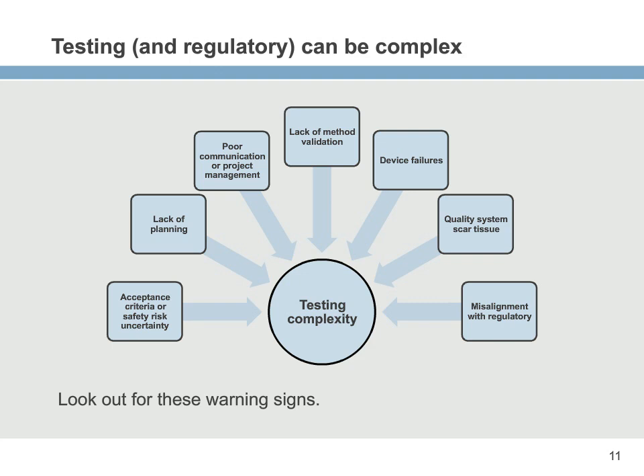Yeah, so if I understand this right, Justin, you have a device failure, and the question would be, is it something wrong with the test, or is it something wrong with the device? And then the flip side of that is with method validation. You can have a test, and hey, it passed the test, but then you ask yourself, well, does the test actually detect any kind of failures? And unless you have a valid method, now you're stuck with saying, well, I'm not sure about my test. So either your test isn't good enough because it doesn't catch bad things, or your test isn't good enough because it creates bad things that it shouldn't create. Yeah, or furthermore there, you didn't understand the uncertainty, you didn't use the right equipment, and the test overall isn't repeatable. So there's a lot that goes into method validation, and we could do a whole talk about that.